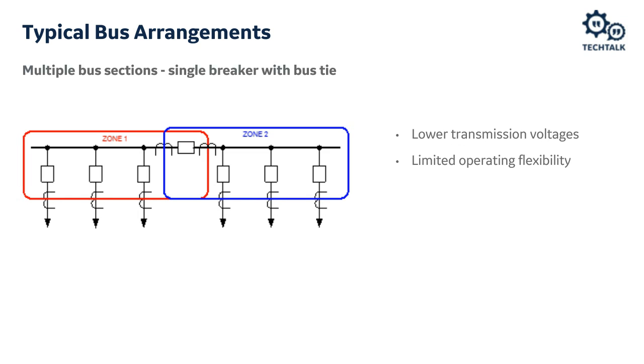Building on the single bus design, we have the multiple bus section or single breaker with bus tie design — commonly referred to as main-tie-main schemes — seen a lot in industrial applications at lower voltages. It offers limited operational flexibility: zone 1 and zone 2 loads each carry roughly 50% of the load. If one bus zone is lost, we can pick up 50% of load on the other bus, providing some reliability and the ability to maintain one bus while keeping loads in service.